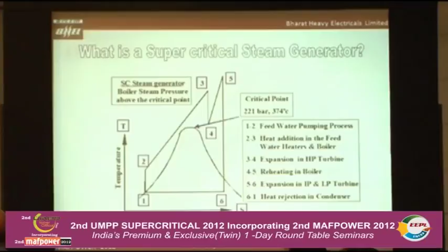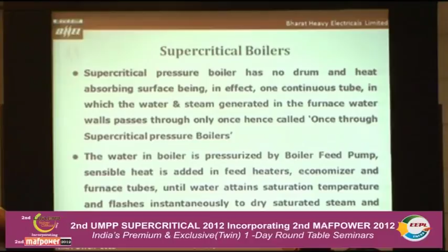So just to touch upon the basics, you are aware that any boiler operating above 221 bar pressure is called a supercritical boiler. And this supercritical boiler, as you are aware, has no drum, which is a huge reservoir-like thing that can take up all the fluctuations in the load and other things. Since the drum is not there, it has a plus and a minus. In the drum, we have an elaborate mechanism even to send chemicals for conditioning the water. Feed water conditioning can be done to some extent, and you can do the blowdown. You can open the blowdown valves and control the feed water chemistry. But such things are not possible in a once-through boiler because there is no drum.